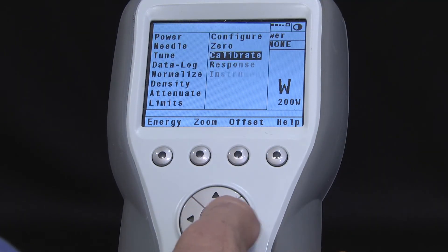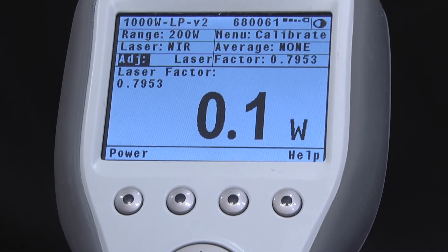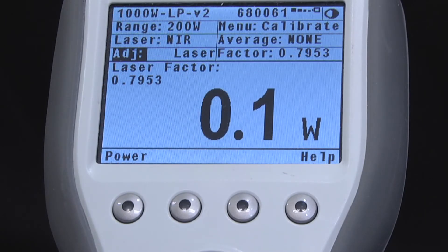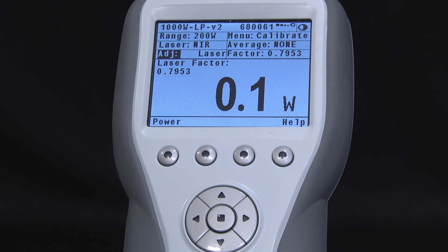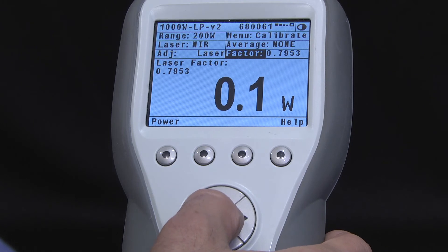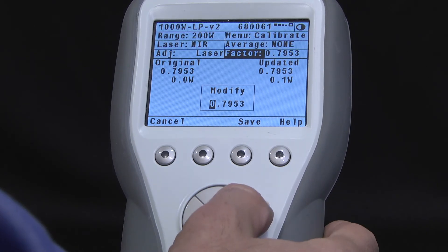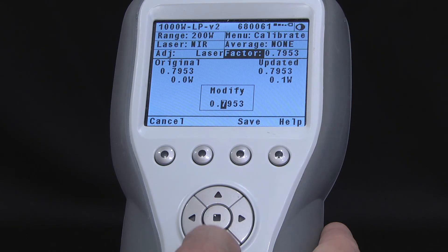On an actual instrument, go to Calibrate in the main menu and set it to Adjust Laser — that is, adjust the calibration factor for just this laser wavelength as opposed to all wavelengths together. Laser factor 0.7953 shown here is the final factor, normally factory-set, for the selected wavelength. In this case, near infrared means 1064 nanometers, and it includes both Factor 1 and Factor 2. This field is user adjustable — pressing Enter opens a modify window allowing you to change it, and saving that change updates the laser factor accordingly.